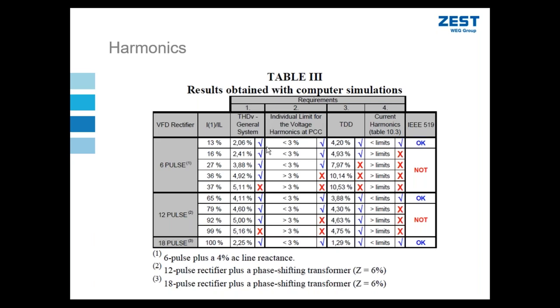specified in IEEE 519. Just for the purpose of this presentation, the one that I'm going to concentrate on is this first one, which is arguably the most important limit in that standard, and that is the total harmonic distortion of the voltage for a general system in IEEE 519. It specifies that this THDV for a general system at the point of common coupling between the customer or the plant and the utility, for example Eskom, must not exceed 5%.